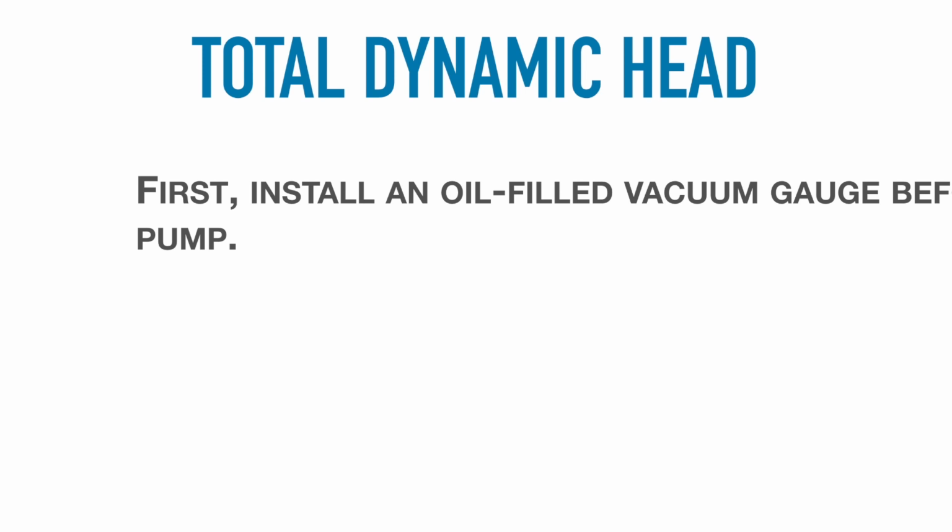Now, for some reason, my slide is being goofy here, so I apologize about that. What you're going to want to do is make sure you write this one down, because it's going to help you on the test itself. We're going to install an oil-filled vacuum gauge before the pump. An oil-filled vacuum gauge before the pump. I know on the slide it just says BFA, but it's actually before.